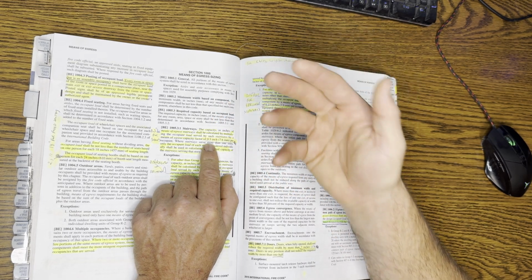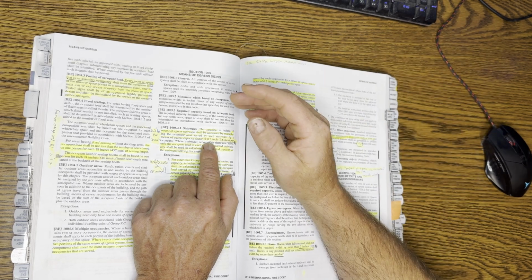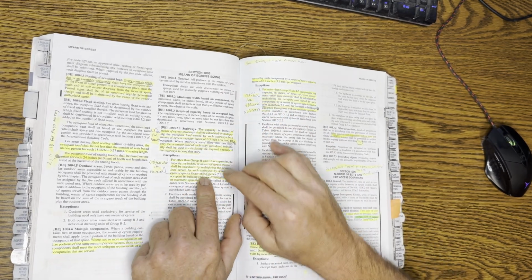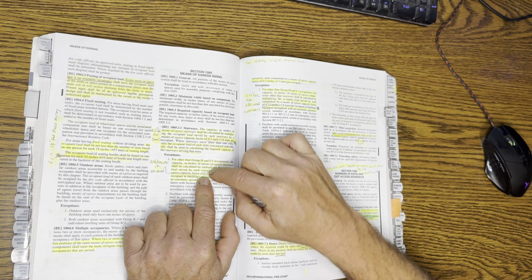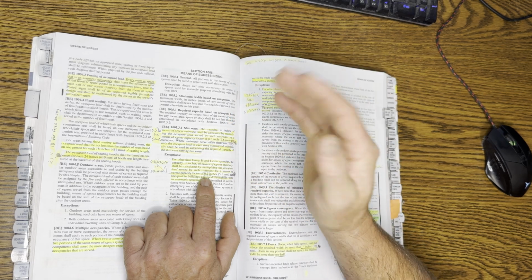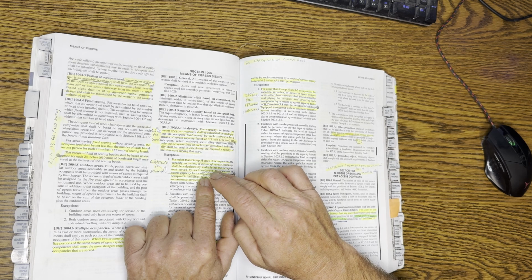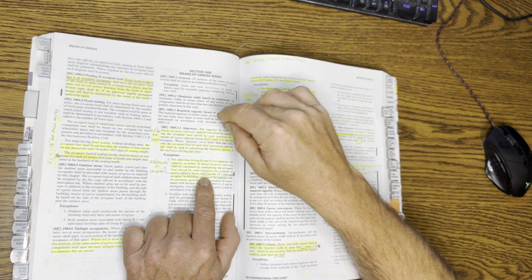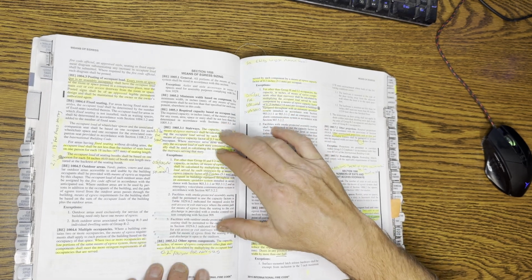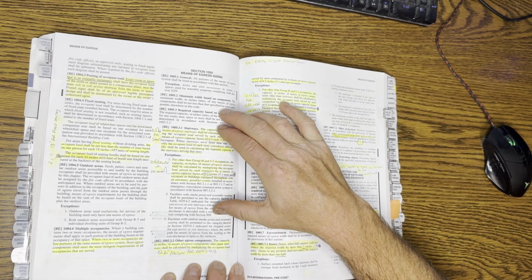So whatever that is, 3 times 44, that'd be a little bit more than that. But the point is, that stairwell would be able to handle like 150 people. Just do the numbers, I'm doing it in my head. Now, down here, if it's suppressed, that stairway, you can use 0.2. So instead of like 150 people for an unsprinklered stairway, down here it's more like 220 people if you have sprinkler capacity. And I want to be very clear, NFPA 101 does not allow this allowance for suppression. So this is just an IFC thing. If you're doing an NFPA related fire inspector certification, this is going to be a little bit different.